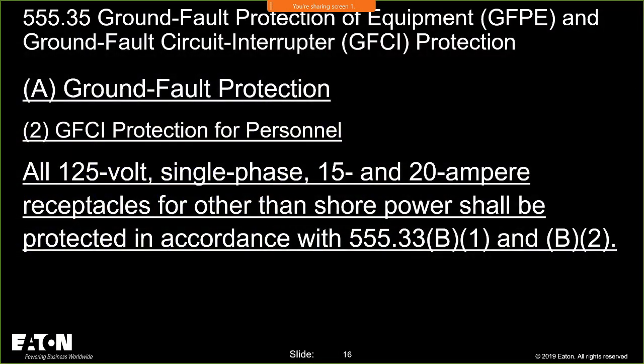They said you have to have GFCI protection on all 15 and 20 amp receptacles for other than shore power. So you have 100 milliamps on feeders going out to the pier, 30 milliamps going to the boats.